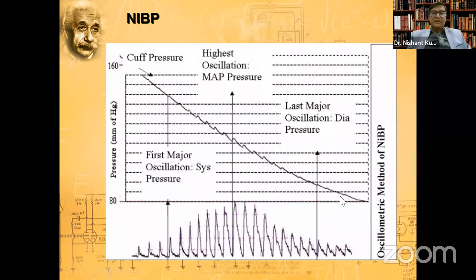Now, as the pressure rises, it might rise linearly or in steps, like 2 mmHg, 4 mmHg, 6 mmHg. If it rises in 1 mmHg steps, it's better. The lower the step, the better it is. A linear rise is obviously better than a stepwise rise of pressure. Now, at some point there will be a total occlusion of the artery because the pressure outside is occluding it. So there will be no oscillations.